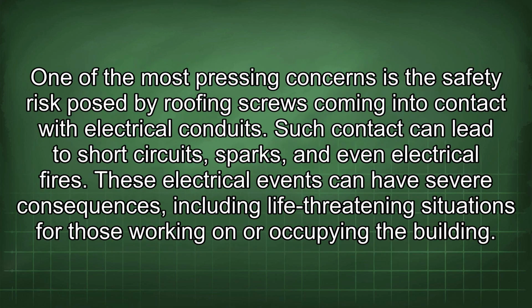One of the most pressing concerns is the safety risk posed by roofing screws coming into contact with the electrical conduits. Such contact can lead to short circuits, sparks, and even electrical fires. These electrical events can have severe consequences, including life-threatening situations for those working on or occupying the building.